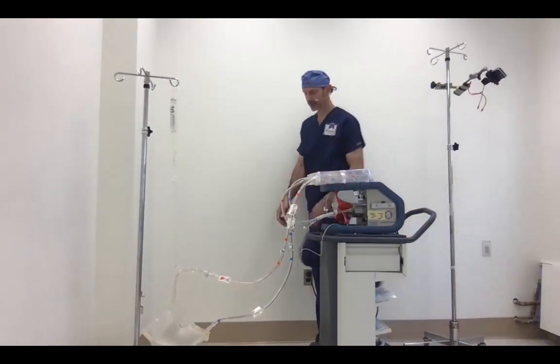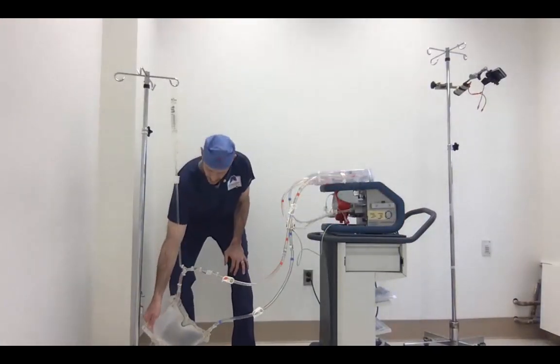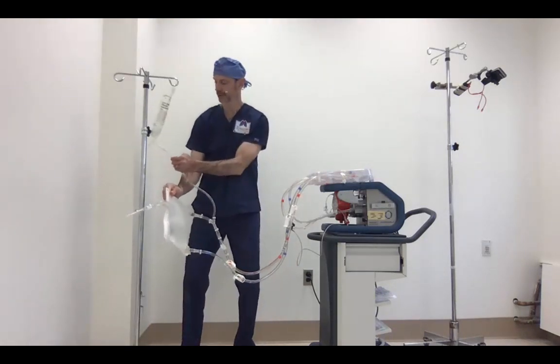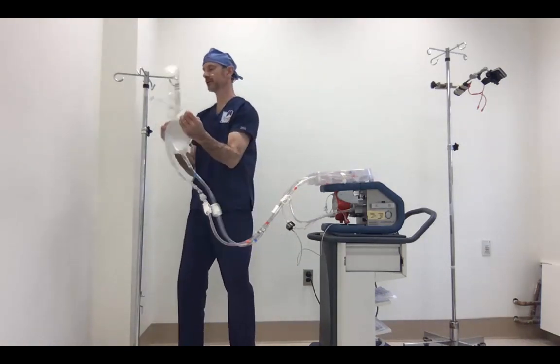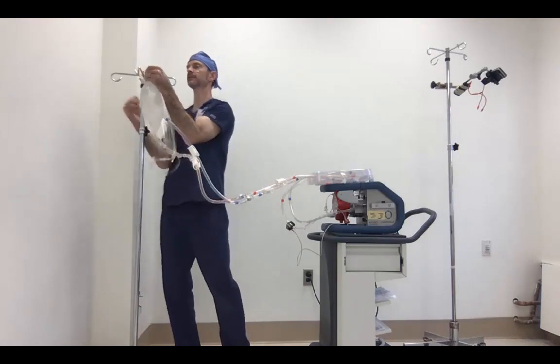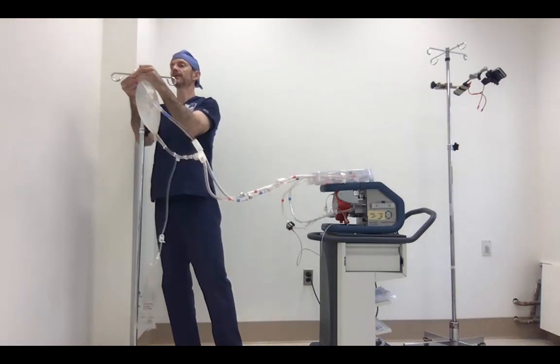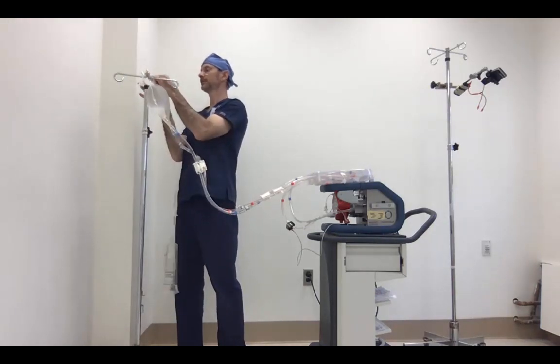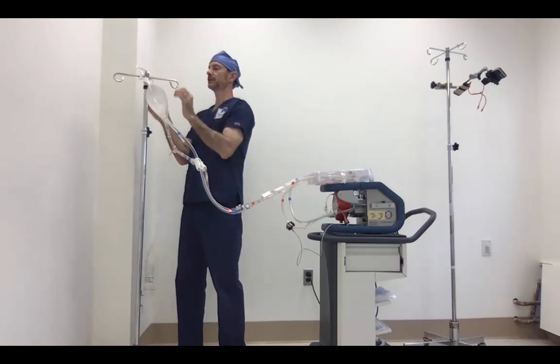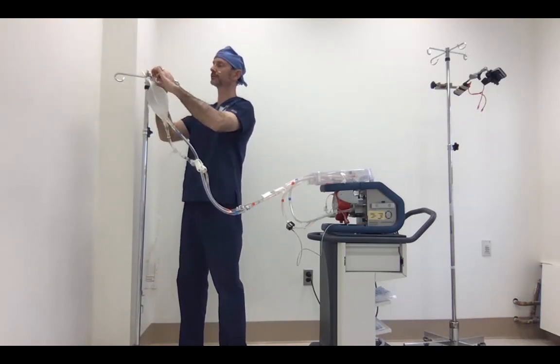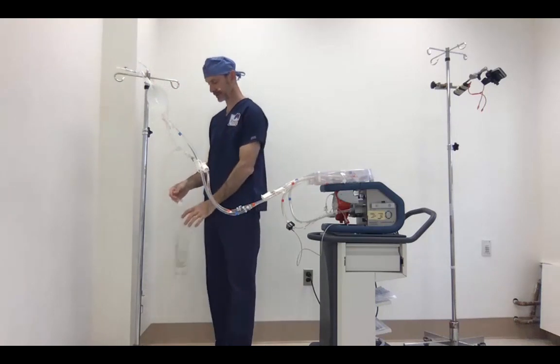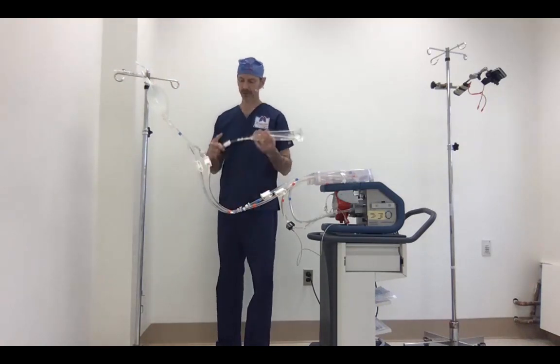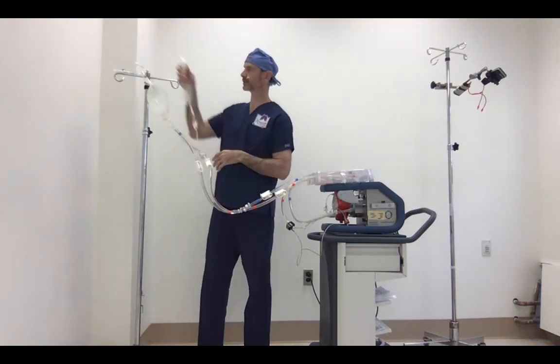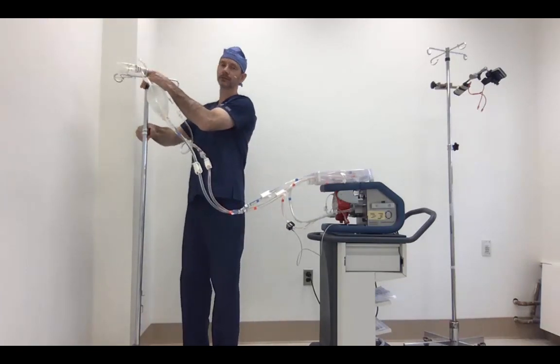Now I let this bag hang low here so it would fill by gravity while I was working on the transducer zeroing. So we'll pick that back up now. And I'm going to have to raise the bar up a little bit and get more height. Make sure you close this clamp or your water will run back into that bag. Work on some height.